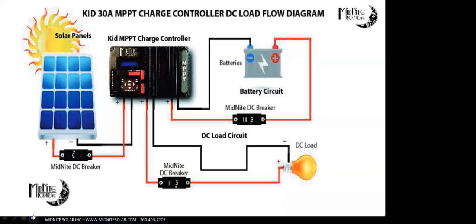We talked about this a bit already—it's called overdriving the charge controllers. Just like a grid tie inverter, our charge controllers can handle being overdriven. I do want to caveat that not every manufacturer will tolerate it—some regulate slower and you'll get nuisance tripping of breakers. So if you're not using a MidNite product, talk to the manufacturer, don't take my word on it. But our products will definitely do that.